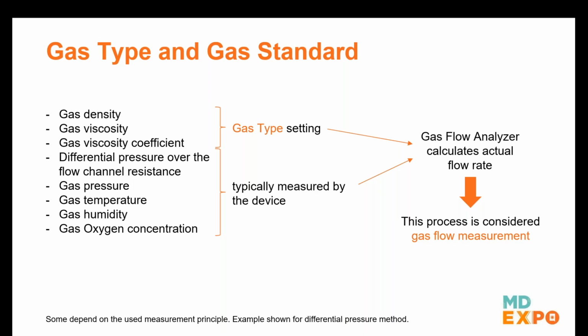Okay? Question? Is there a calculation difference, like a percentage, if you have it set for oxygen? Yes, because they both have different gas densities, right? If you're just using air, it's already 21% oxygen, but if you switched over to 100% oxygen, now you've changed the gas density. So you need to tell your analyzer, I'm measuring 100% oxygen, or let its sensor tell you what it's measuring. You have two choices.